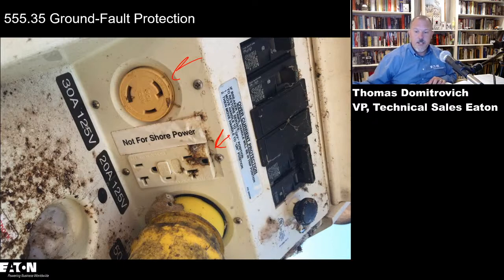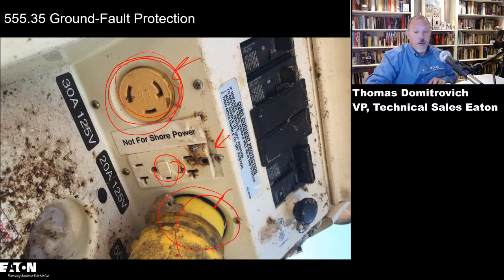All right, so it has to be indicated, and it is GFCI protected. And now, per the new version of the code, this will have to be GFPE protected at 30 milliamps. This will have to be GFPE protected at 30 milliamps. And I'll tell you how they get it done. They're going to get it done by putting GFPE in the breakers that supply power to those receptacles.